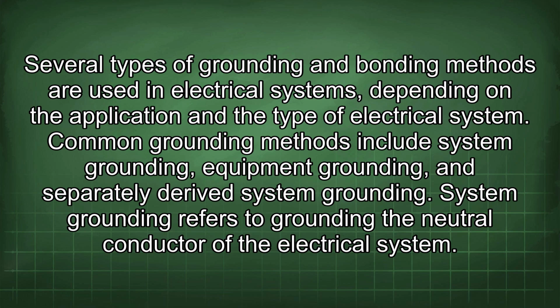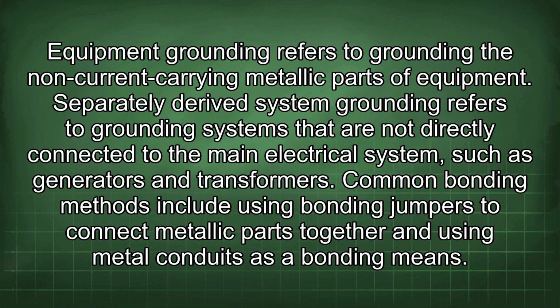System grounding refers to grounding the neutral conductor of the electrical system. Equipment grounding refers to grounding the non-current carrying metallic parts of equipment. Separately derived system grounding refers to grounding systems that are not directly connected to the main electrical system, such as generators and transformers. Common bonding methods include using bonding jumpers to connect metallic parts together and using metal conduits as a bonding means.